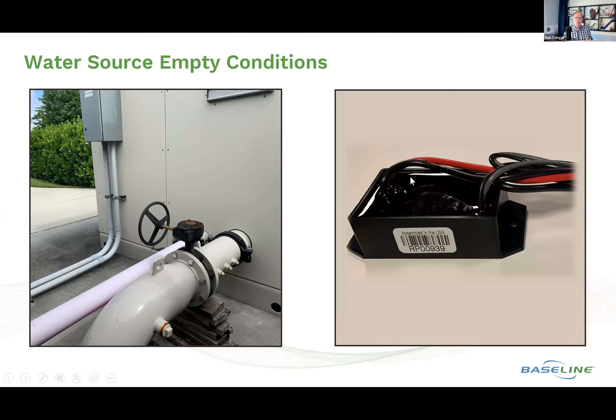Another water source empty condition can be based on an event switch using the BL-5402 event bicoder. Large pump stations — like this one capable of 1,800 GPM — often have their own control systems with indicator lights or switches. The BL-5402 event bicoder can read a third-party switch condition and allow it to influence the Baseline system, so we can connect an external indicator to control whether a water source is considered active or not.